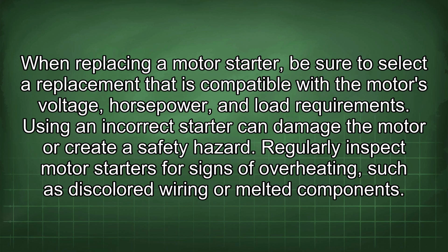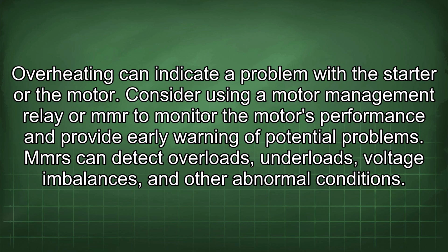When replacing a motor starter, be sure to select a replacement that is compatible with the motor's voltage, horsepower, and load requirements. Using an incorrect starter can damage the motor or create a safety hazard. Regularly inspect motor starters for signs of overheating, such as discolored wiring or melted components. Overheating can indicate a problem with the starter or the motor.